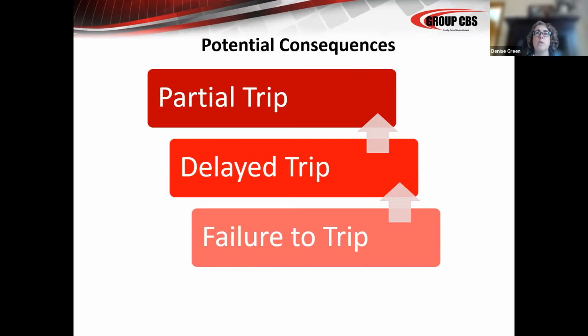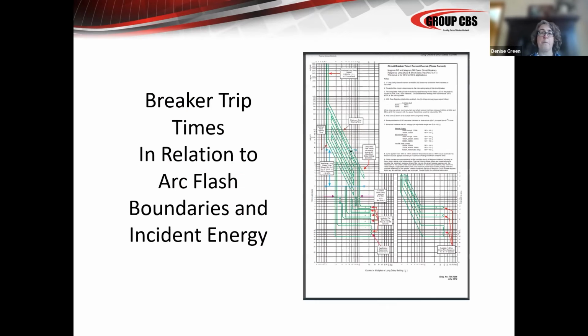Okay. So yeah, and now when we get to the 1584, we're going to talk about the 240 volt component to all of this, considering that. So are we good on the partial trip? Okay. So now we're going to talk a little bit about trip times in relationship to arc flash. And this directly goes to breaker maintenance and breaker condition.